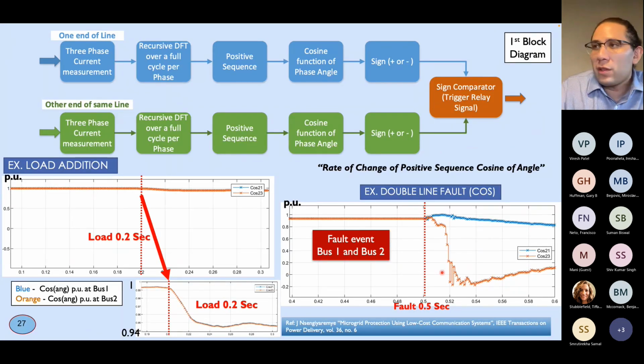So the first method shown here, basically we have a three-phase current. We pass it to a recursive DFT. We obtain the positive sequence. We obtain the cosine function of the phase angle. We decide whether it's positive or negative, and by this comparison, we can trigger a relay to identify if there is a fault or not, which is shown in the bottom figure at 0.5 seconds. On the left-hand side, we see that there's no trip.